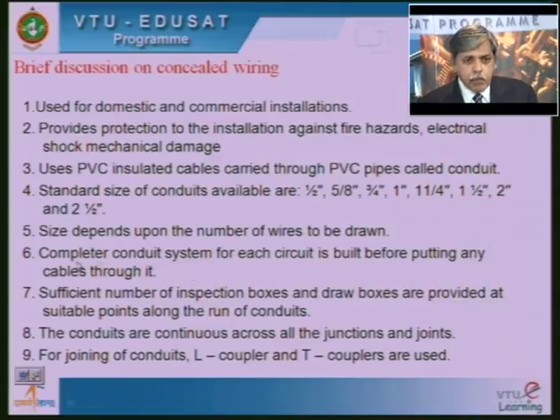This is a complete conduit system: for each circuit, it is built before putting any cables through it. What do you mean by this? If you see any house construction, before placing the roof, the electrician will come there and he will draw some conduits. There will be a different diagram for each house. I cannot have the same diagram for all the houses. Depending on the number of points you want, that is the plug point, switchboard, lighting points, fan, heating circuits, depending upon all that I will arrange a conduit system there.